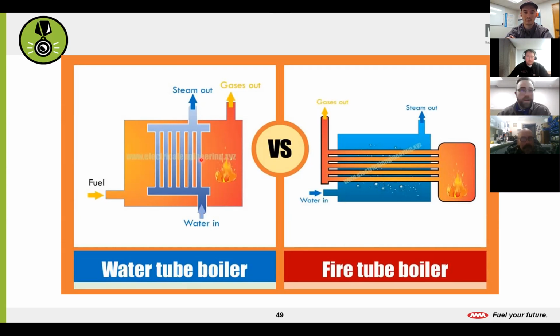But it's actually not. So generally speaking, a fire tube boiler is usually smaller, has a smaller capacity for its application. Usually we see fire tube boilers in building heating, whether that's domestic water or condenser loop heating, stuff like that. Water tube boilers have a much higher capacity and BTU content there. We usually see these much less so in building heating scenarios. These are going to be more towards industrial applications, those kinds of processes. The trade-off is water tube boilers are much more expensive upfront and much more expensive to maintain, whereas a fire tube boiler is cheaper, and maintaining them is usually easier and cheaper over the life of these units. But again, capacity-wise, you get smaller capacity out of your fire tube versus your water tube.